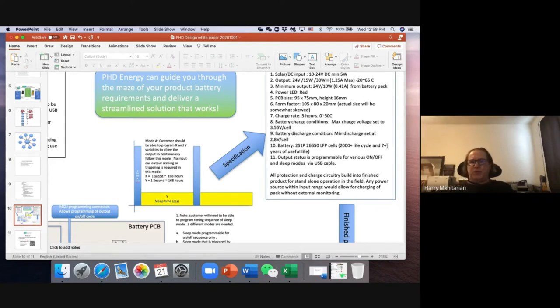It will also ensure they get 7+ years useful life out of the battery, because you're not degrading it as much when charging. It extends that life. The minimum discharge is 2.8, which is typical, so we didn't have to mess with that standard minimum cutoff for an LFP battery.